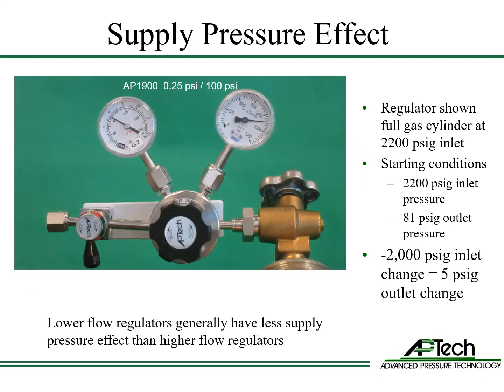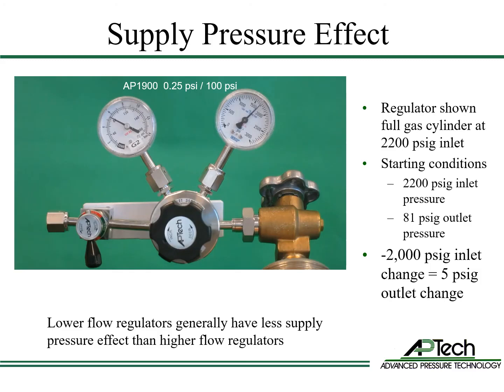Now we will demonstrate the supply pressure effect on the AP1900. Again, the inlet pressure is 2200 psi and outlet pressure is 81 psi. The 2000 psi drop in inlet pressure only causes a 5 psi increase in outlet pressure. The AP1900 supply pressure effect is only 0.25 psi per 100 psi inlet pressure change. Lower flow regulators generally have less supply pressure effect than higher flow regulators.